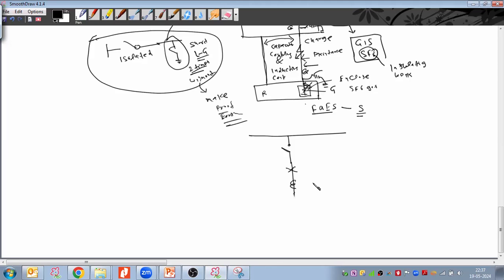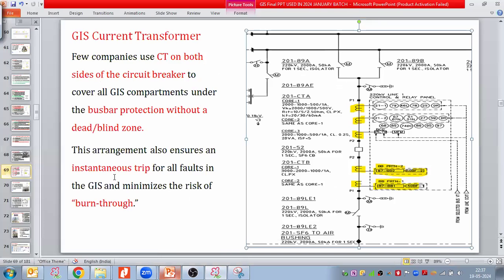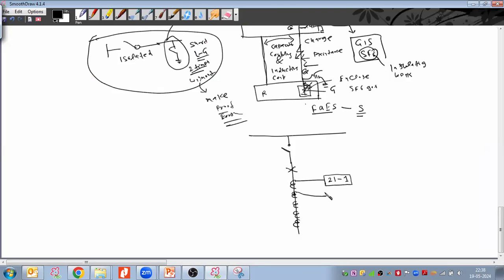Generally, let us take any 220 kV feeder. How many CT cores do we take? Five cores, sir. This core is for the distance protection. This protection module we have not discussed so far. If anyone is not getting my point, do not worry. You just note down the concept. When I take up the protection module, you will get this point easily. I am converting this statement into the SLD, but we have not discussed protection yet. Then there is the metering core.